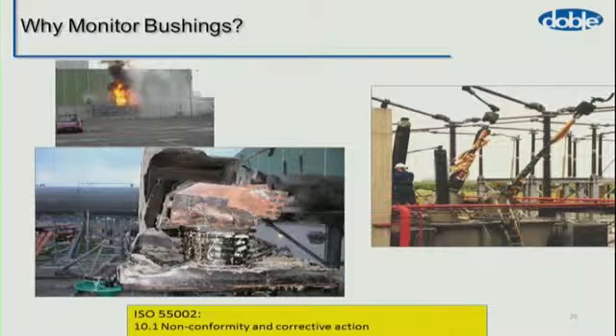Monitor bushings because they fail. In the picture on the right, you can see the bushing on the right failed. The bushing in the middle, which has been taken apart, it did not fail. It was killed by something else, which is the bushing next to it failing, and the explosion which took out that one destroyed the center phase.